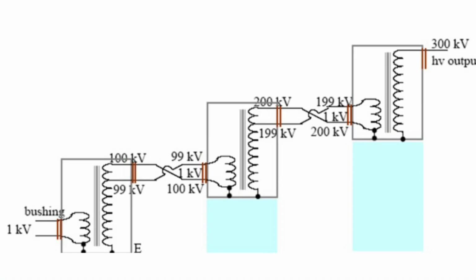Beyond 35 kilowatt, they ask the user to provide a dedicated transformer. And where do high tension and low tension lines come into picture? When total load requirement crosses 150 kilowatt, then a high tension service line is required, and below 150, it is LT based connection. So there's a good thumb rule: beyond 30 kilowatt, mostly you should go for a separate transformer, and beyond 150 kilowatt load, you go for a high tension line.